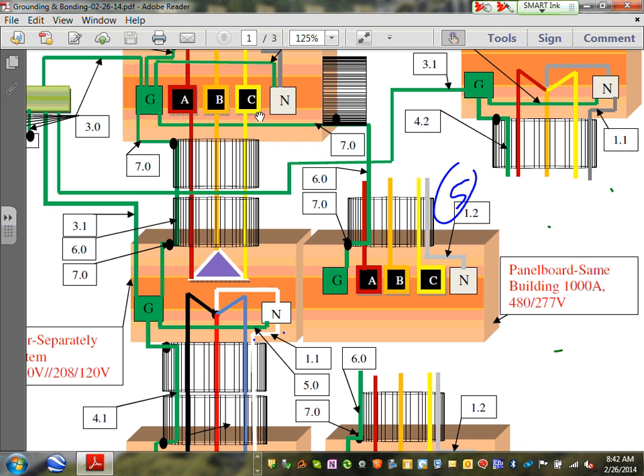Okay, so we have an equipment grounding conductor right here. That's the first thing I'm going to size, the equipment grounding conductor, okay? And right with it, we bond the conduits from both sides. Can you guys see how we bond the conduits from both sides if they're metallic? If they're non-metallic, then you just pull the equipment grounding conductor inside the conduit and move on. That's the first thing you do to the transformer.